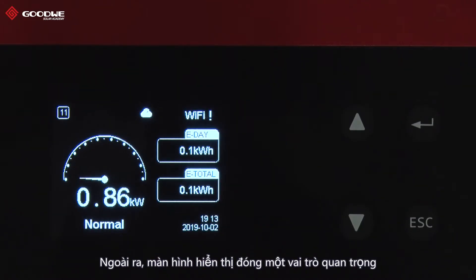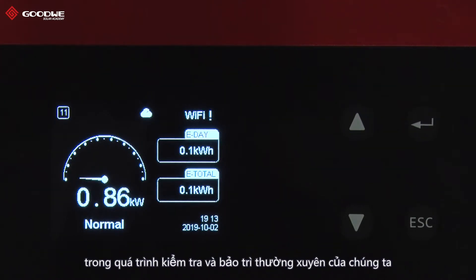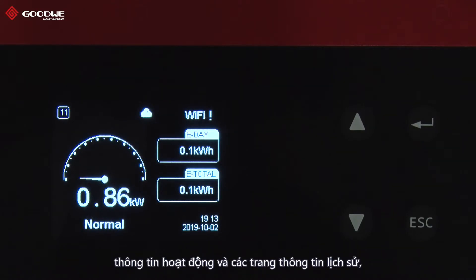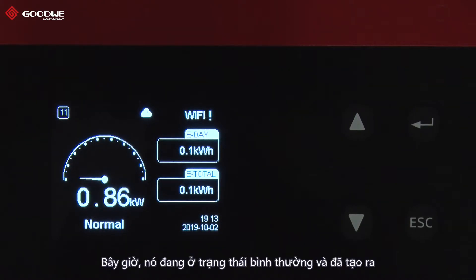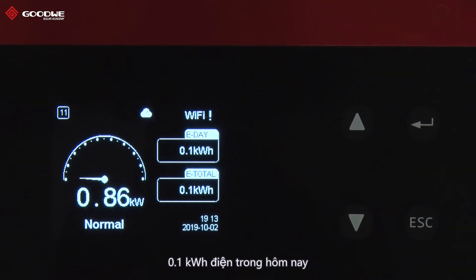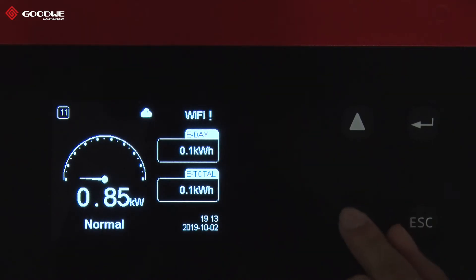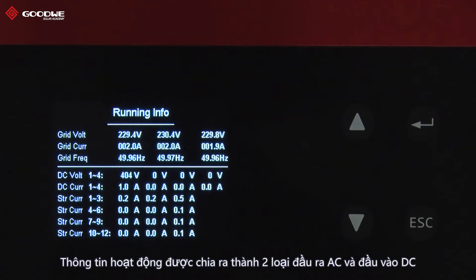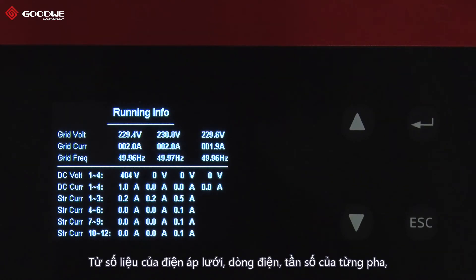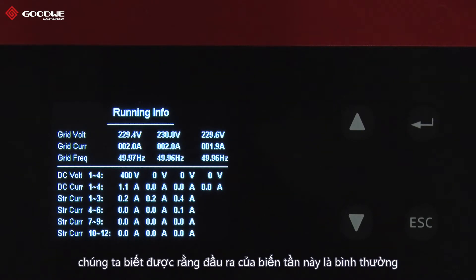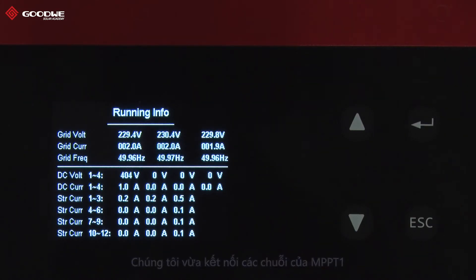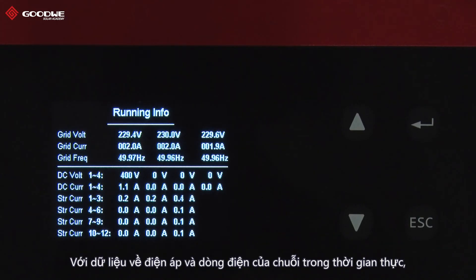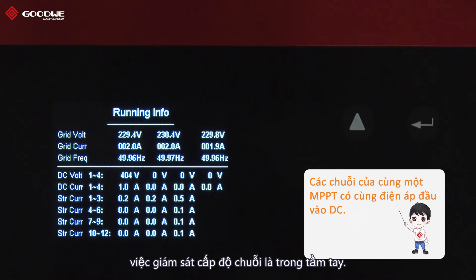In addition, the local display plays an important role in our regular inspection and maintenance. From the home page, running info, and history data pages, we are able to know a lot about the inverter's operation status. Right now it is in normal status and has produced 0.1 kWh of electricity today. Running info is divided into AC output and DC input. From the grid voltage, current, and frequency of each phase, we know this inverter's output is normal. We can also read DC input voltage and current of MPPT1 to MPPT4. Since we connected strings to MPPT1, there are only inputs from string 1 to string 3. With real-time data of string voltage and current, string-level monitoring is at hand.